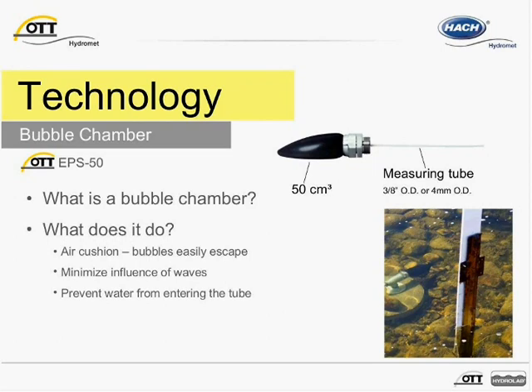Only during extreme cases where the water level increases by 10 feet or more in a short measuring interval would you find water that has actually entered the tube. If a bubble chamber is not used, water may rise into the tube after bubbles have escaped. If water is inside the tube during the pressure reading, the measurement may not reflect the true stage value or level value.